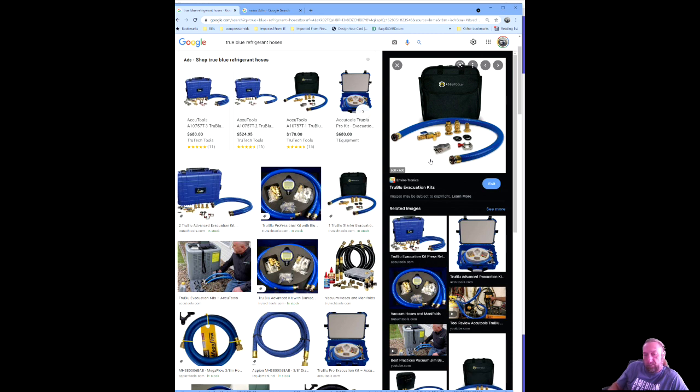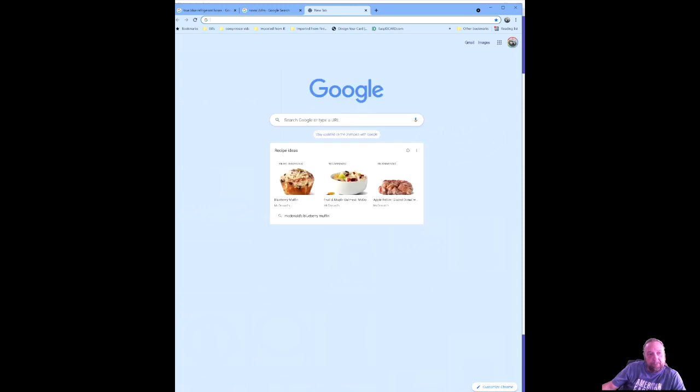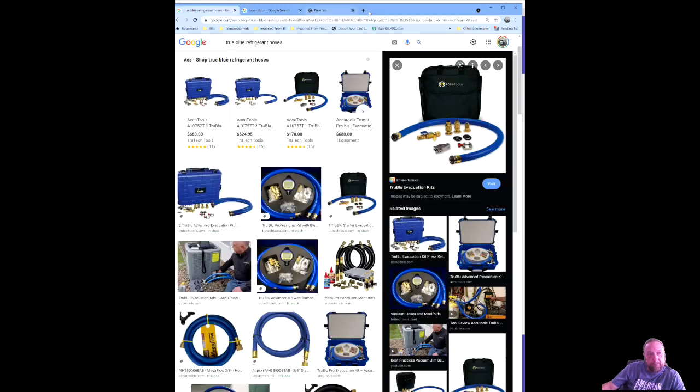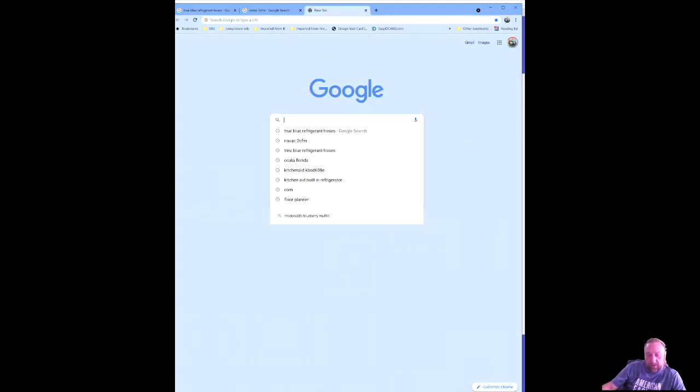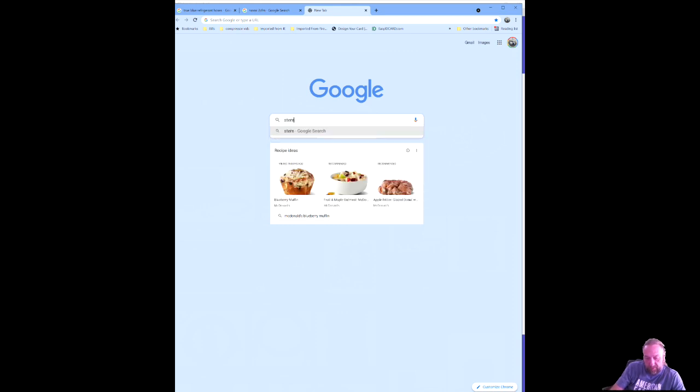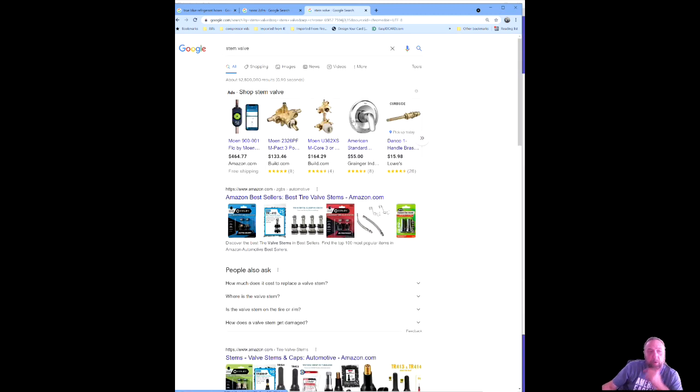It's up to you. Using a piercing valve like pliers or those piercing valves doesn't make sense, because you use that only in the beginning to make the diagnostics, right? Yeah. And you're not pulling a vacuum for that. That would be very difficult. But later on, when you solder on the Schrader valve or the valve that comes on the dryer, you can use that. Well, that's when you pull the vacuum.